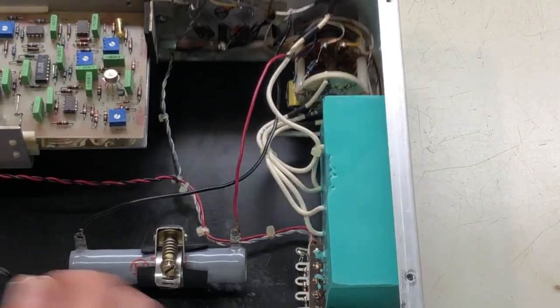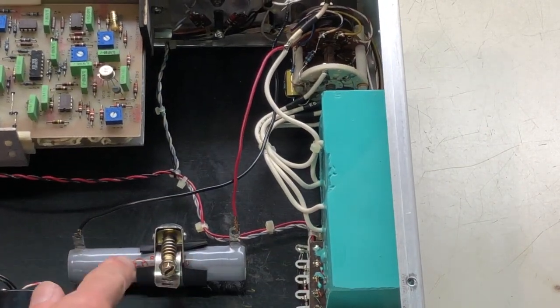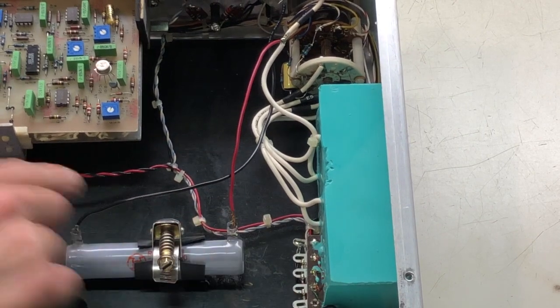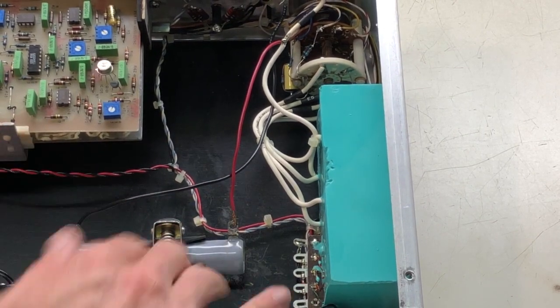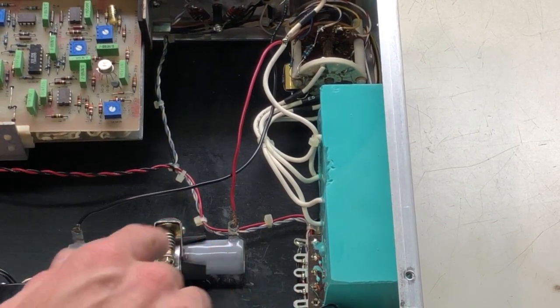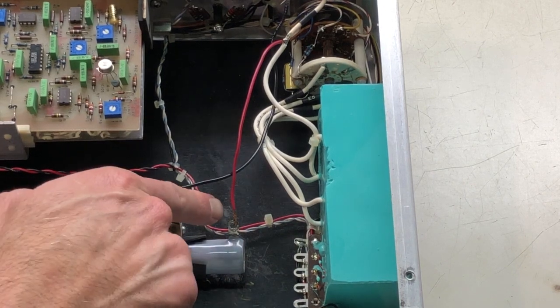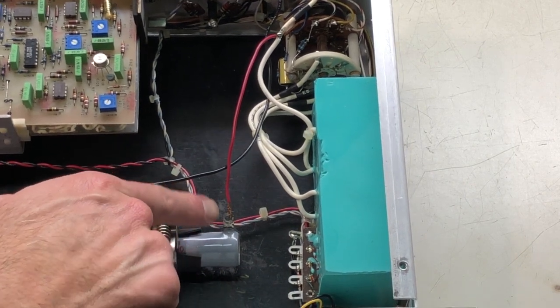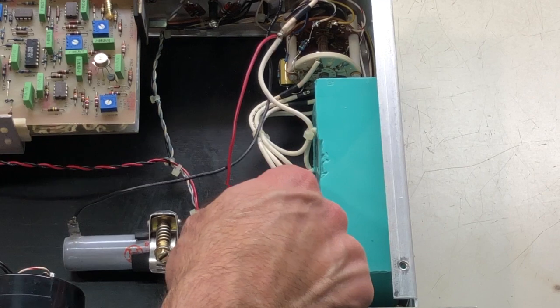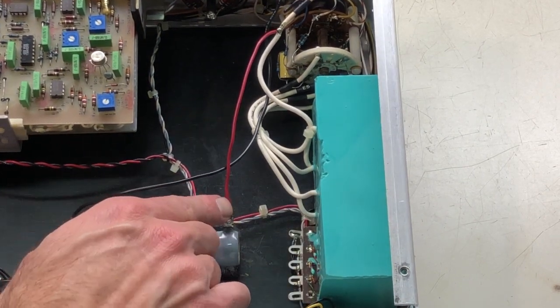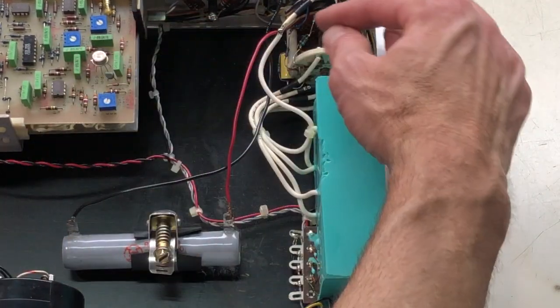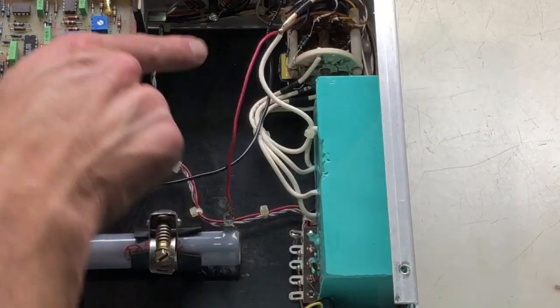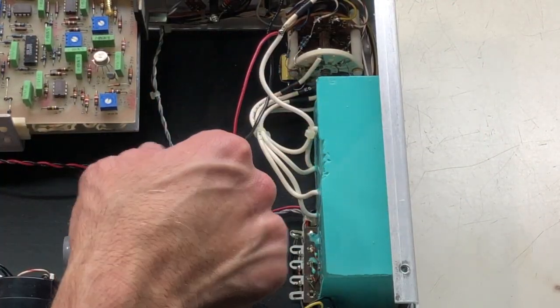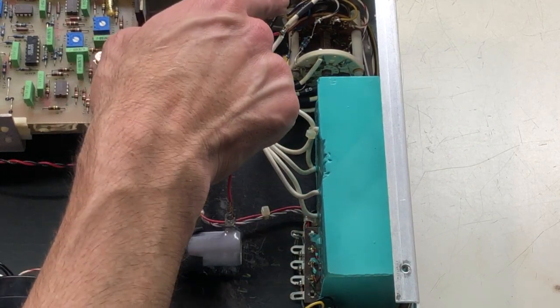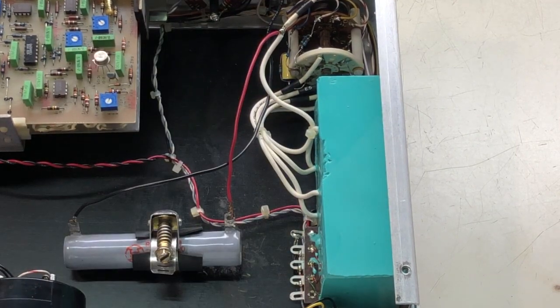Whatever this resistor is that someone added in here, it's kind of mounted in here, and it's got this hose clamp around it, and they've got some rubber, and then looks like they've got some wire. That is not soldered very well there at all. This terminal, I don't know what's going on there. That doesn't look like a good solder at all. It looks like they stripped the insulation back on this high voltage lead and tied in right here with a little bit of solder and brought that, and a ground wire here, and they did the same thing. That definitely needs to be cleaned up.